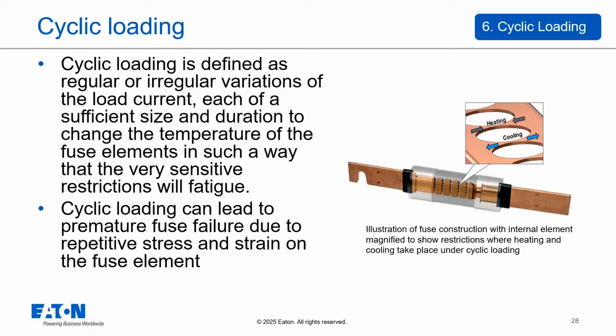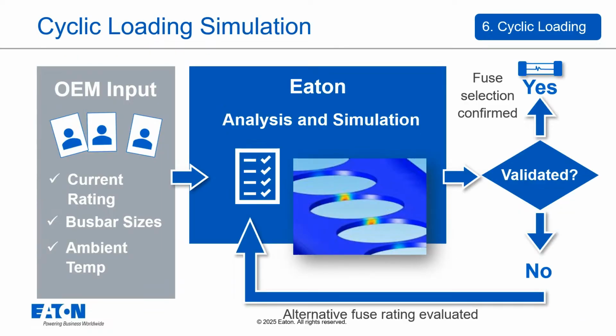Given the complexity of real-world EV drive cycles and the impact of cyclic loading, how do we ensure a fuse will last? Eaton offers EV fuse simulation capabilities. Customers provide their application's specific load profile, plus things like busbar sizes, ambient temperature, and the expected current patterns over time. Eaton can then use analysis and simulation tools to model how the fuse will behave under these conditions and estimate its cycle life. The big benefit of simulation is that it helps confirm the fuse selection before costly and time-consuming physical validation testing. It enhances confidence and can shorten the project timeline. Custom drive and charging profiles can be simulated against the fuse's known fatigue characteristics to help suggest the required fuse ratings for a specific application.